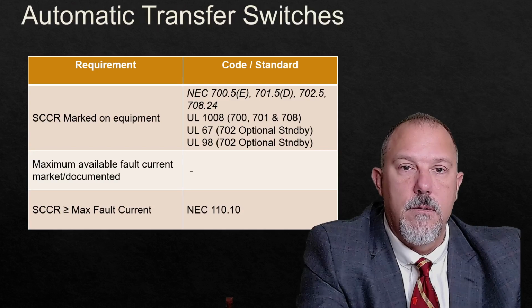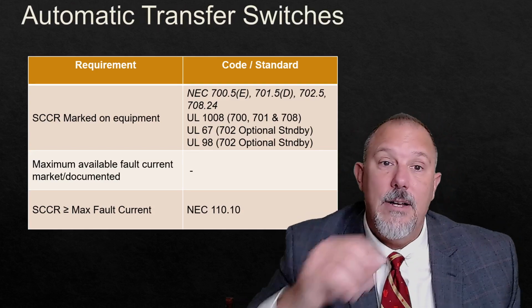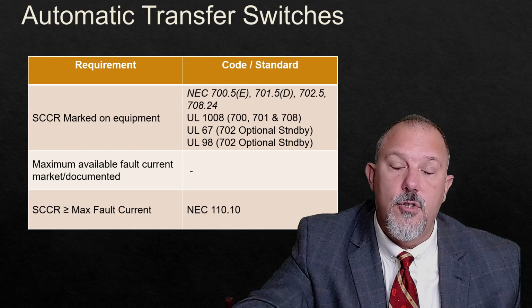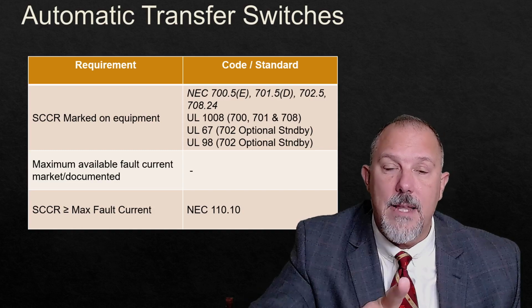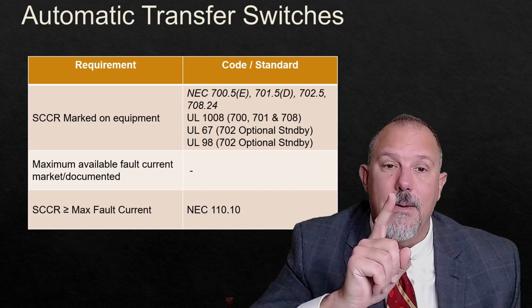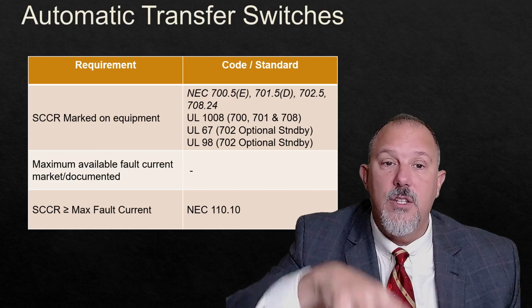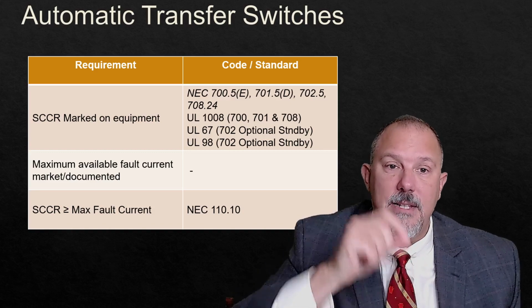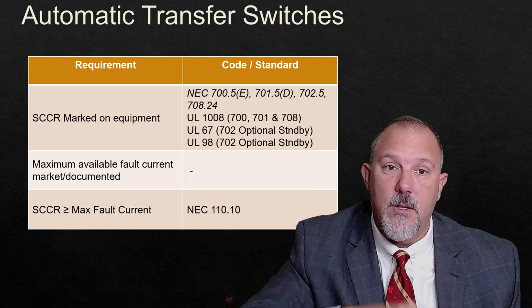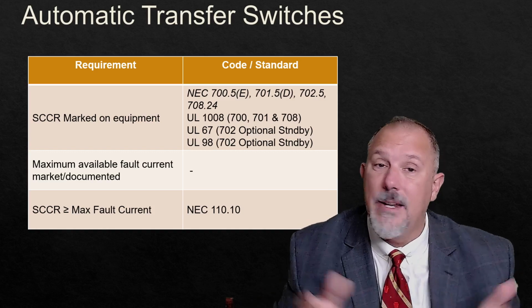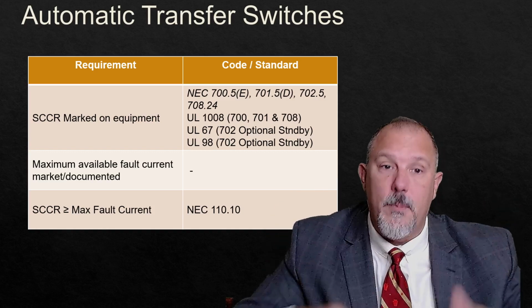Automatic transfer switches. Let's get this right. Article 700, 701, 702, and 708. UL 1008, UL 67, UL 98. All of these, if they're a listed product, the SCCR is required to be on there based on the sections of the code. But if you buy a listed product, they're required to be on there based upon the standard.